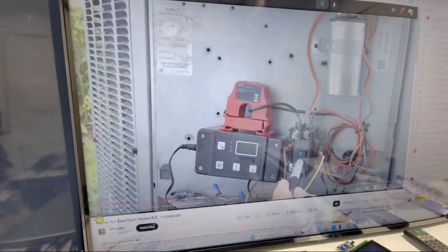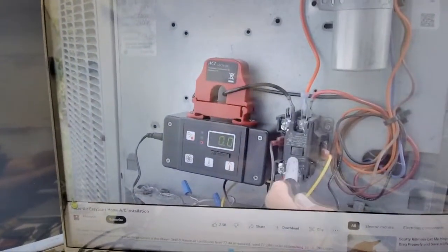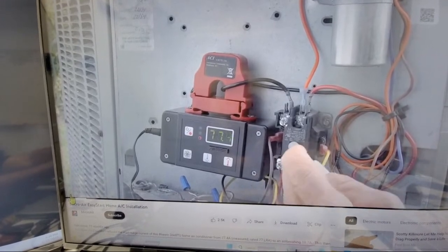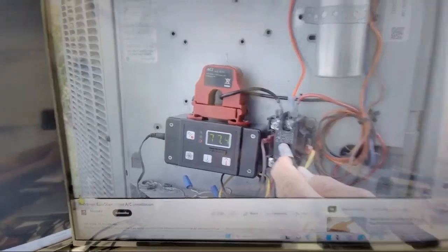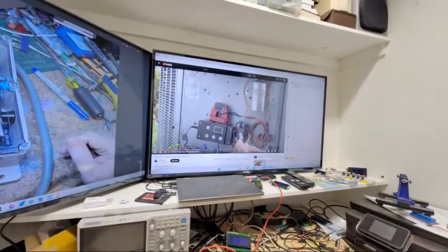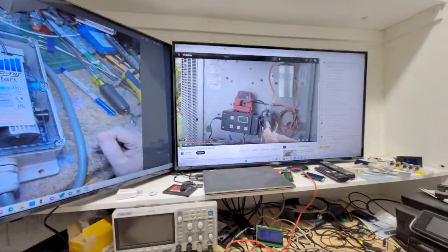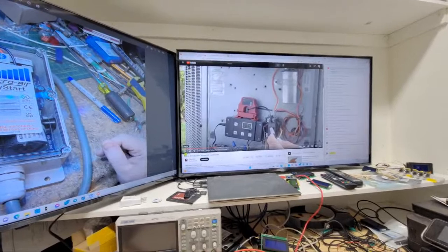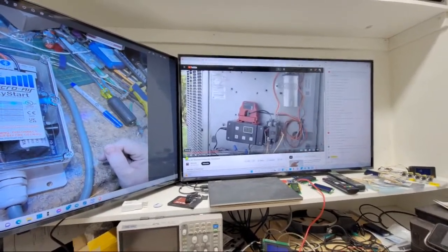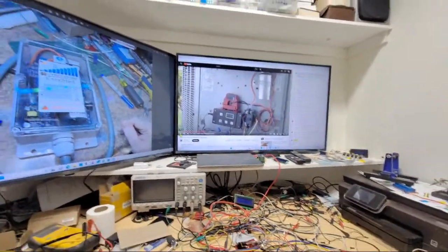Once we have the Easy Start installed. So here we go. We're going to start the compressor without Easy Start and see what the peak current is. All right. So there it goes. Running it for a little bit. By the way, that outdoor fan motor is toast on this unit this guy's using. Listen to those bearings. So he got 77 amps.